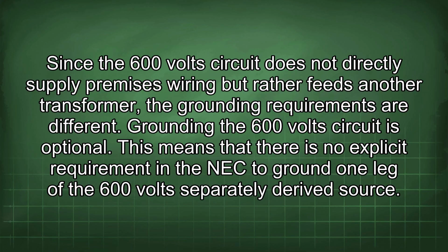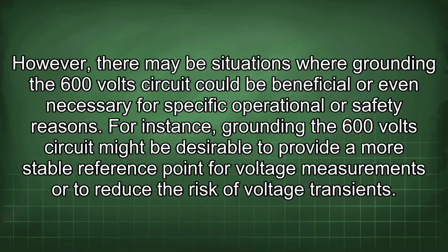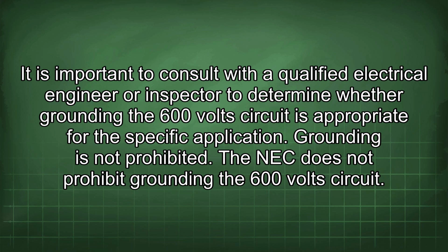This means that there is no explicit requirement in the NEC to ground one leg of the 600 volt separately derived source. However, there may be situations where grounding the 600 volt circuit could be beneficial or even necessary for specific operational or safety reasons. For instance, grounding the 600 volt circuit might be desirable to provide a more stable reference point for voltage measurements or to reduce the risk of voltage transients. It is important to consult with a qualified electrical engineer or inspector to determine whether grounding the 600 volt circuit is appropriate for the specific application.